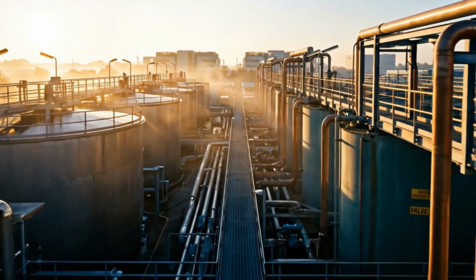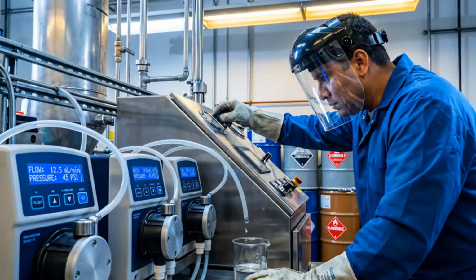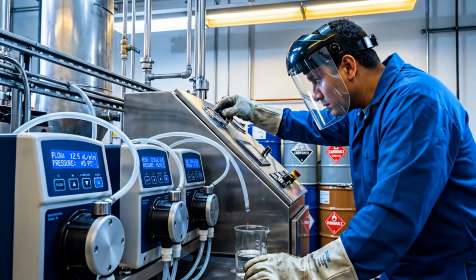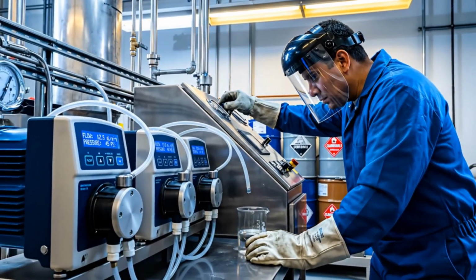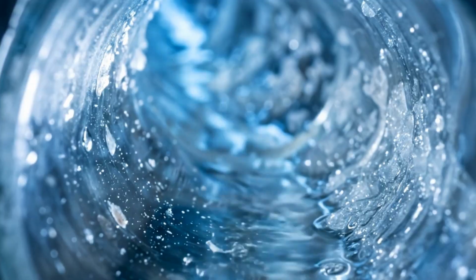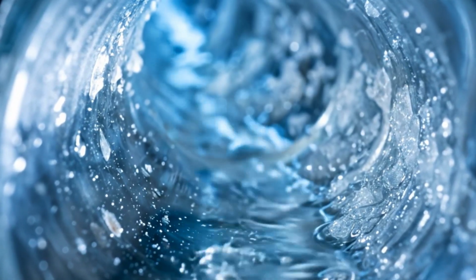Water consumption is only part of the problem. The other part is what happens after the water is used. Cooling systems rely on chemical treatments to prevent corrosion, mineral buildup, and biological growth. As water circulates, it picks up salts and chemical residues.